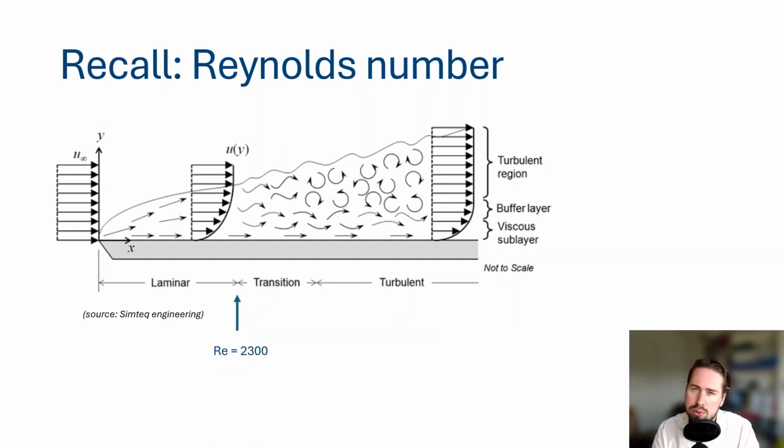And around a Reynolds number of 2300, we know that the fluid becomes more and more transient. We move towards a turbulent regime where the fluid droplets and particles tumble across each other, and we make sure that they touch the pipe at one point or another. So the heat transfer increases, it's better, and around a Reynolds number of 4000, we have a fully developed turbulent flow. Now, although the heat transfer is better in a turbulent flow, the pressure drop also increases because you need more pump energy, more pump power to really get this fluid into this turbulent flow.